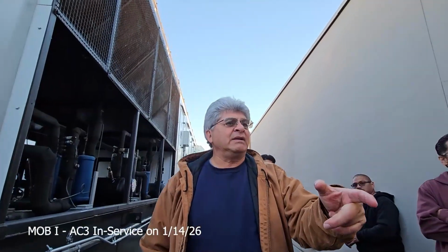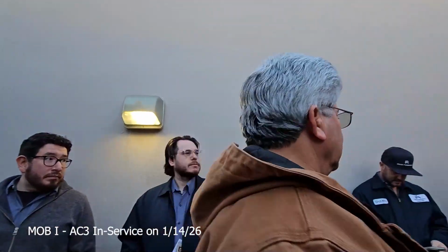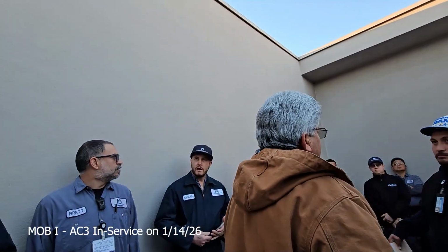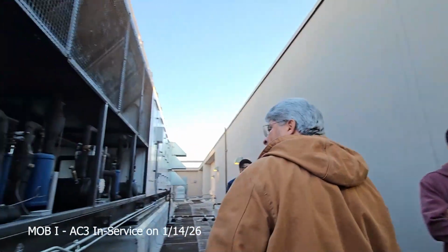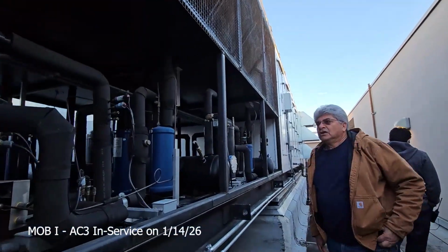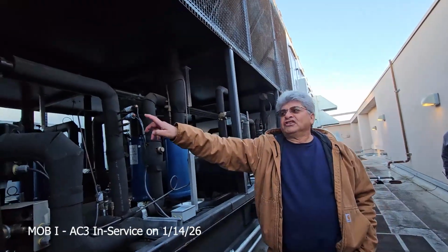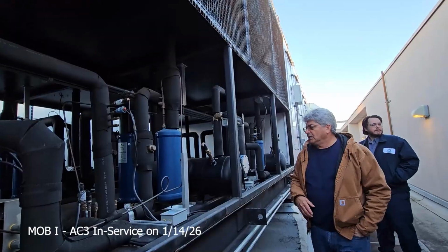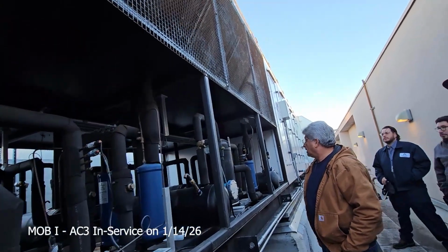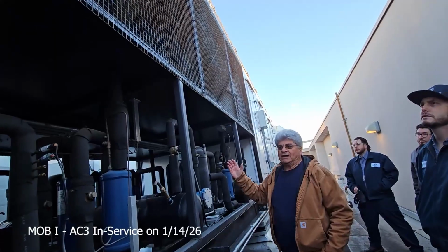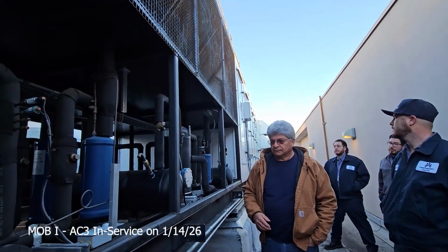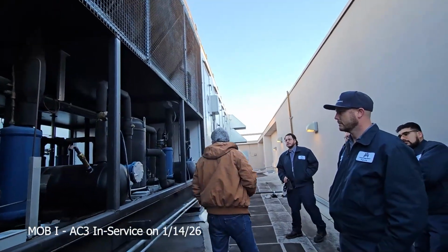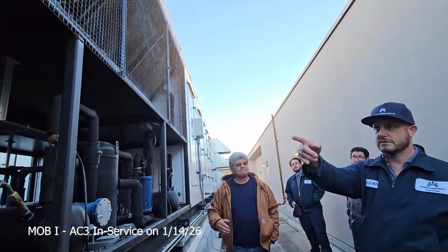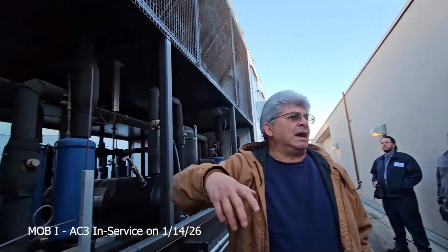Did you want me to spend any time talking about your condenser section? Any common things we need to reset? Any things we need to be checking on our end? That's the only random reset there. Nothing else to reset out here. So there's no safeties or anything for us to reset out here by the compressor? Just the high pressure? Everything's redundant on every circuit.